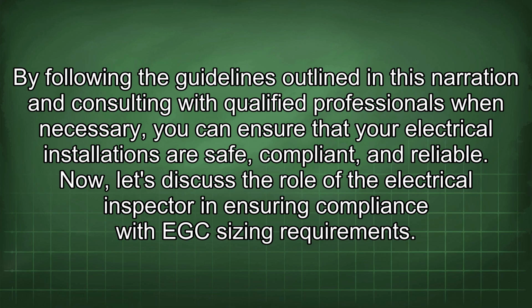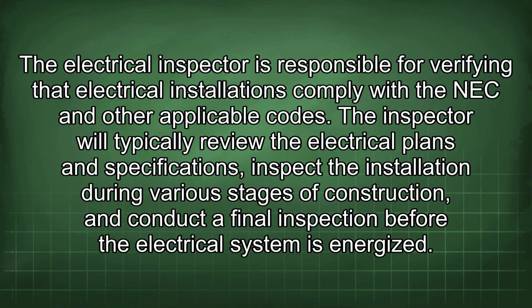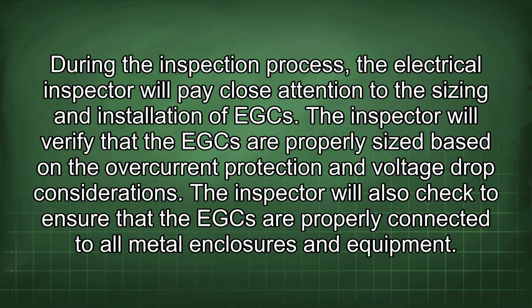Now let's discuss the role of the electrical inspector in ensuring compliance with EGC sizing requirements. The electrical inspector is responsible for verifying that electrical installations comply with the NEC and other applicable codes. The inspector will typically review the electrical plans and specifications, inspect the installation during various stages of construction, and conduct a final inspection before the electrical system is energized. During the inspection process, the electrical inspector will pay close attention to the sizing and installation of EGC. The inspector will verify that the EGC are properly sized based on the overcurrent protection and voltage drop considerations. The inspector will also check to ensure that the EGC are properly connected to all metal enclosures and equipment.